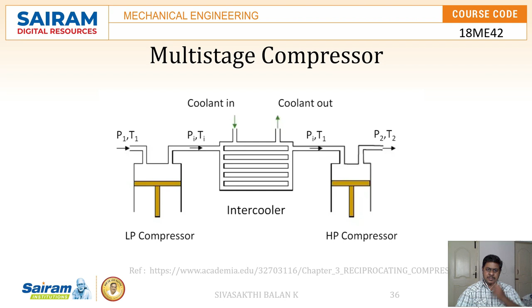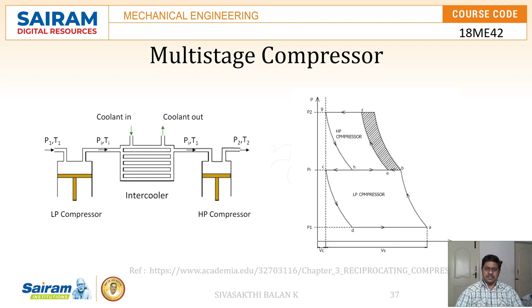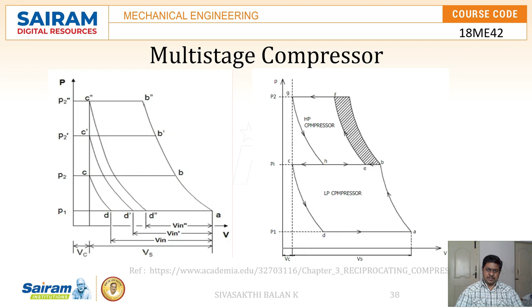When you observe the PV diagram for the double stage compressor, it shows a drastic decrease in the work input. The shaded portion explains that. Now let us compare a single stage compressor with a double stage compressor for the same pressure ratio. For the same high pressure delivery condition, the induced volume for the single stage compressor is far less than for the double stage compressor. This is the main drawback of using a single stage compressor.